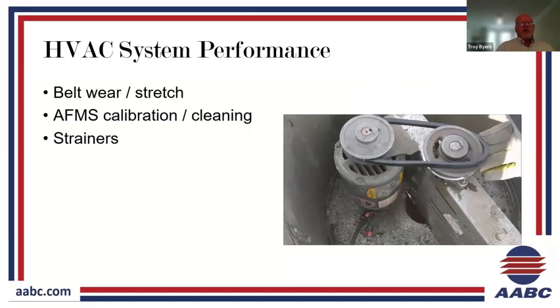So part of an ongoing and periodic TAB of existing buildings, if you have a program of periodic maintenance, one of our points of failure is belts. I mean, these belts should be inspected annually, but in many cases, out there in the field, we see many cases where we know that these belts have not been changed or tested or checked in years. So that's a point of failure there.